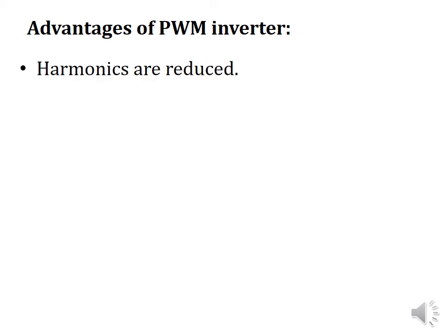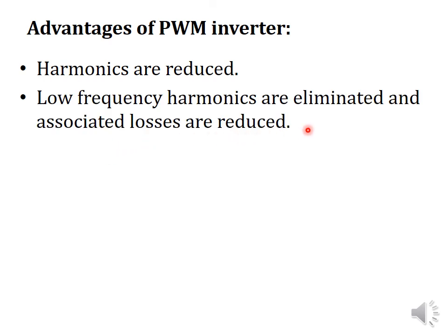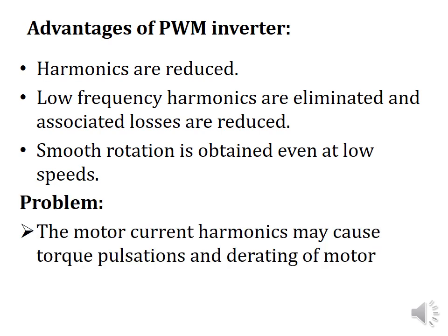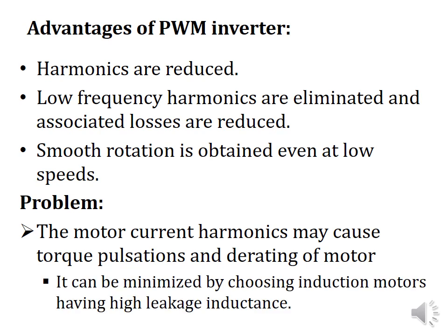The advantages of a PWM inverter for controlling an induction motor: harmonics are reduced, low-frequency harmonics are eliminated and the associated losses are reduced, and smooth rotation is obtained even at low speeds. However, it does have one drawback: motor current harmonics may cause torque pulsations and derating of the motor. To minimize the motor current harmonics, we can use an induction motor with high leakage inductance.